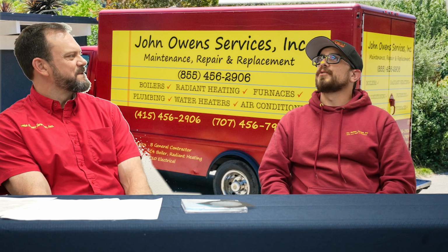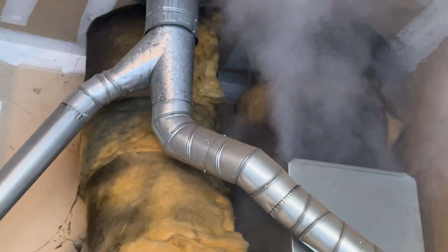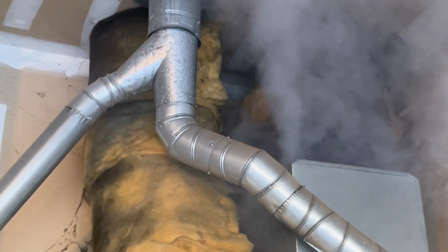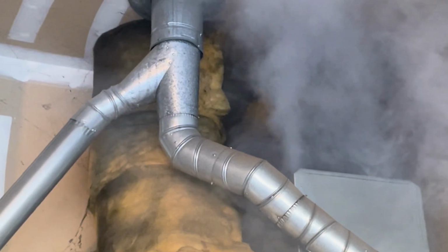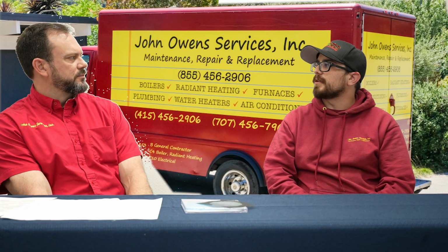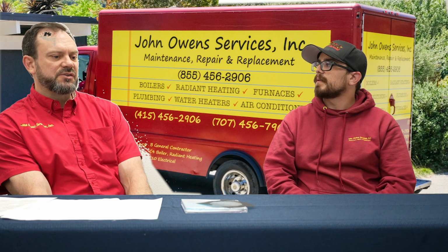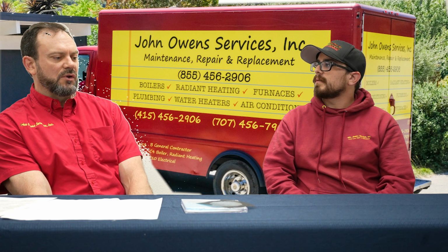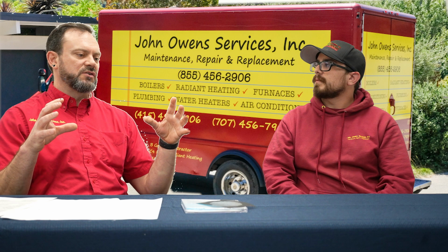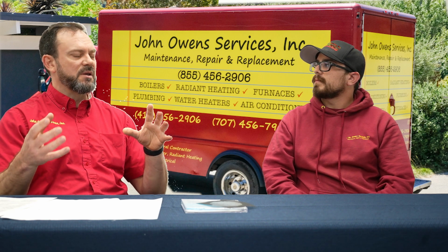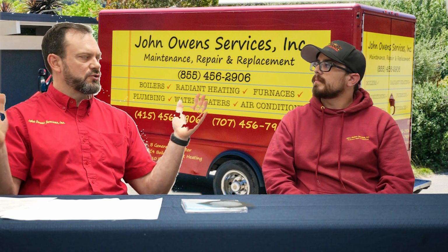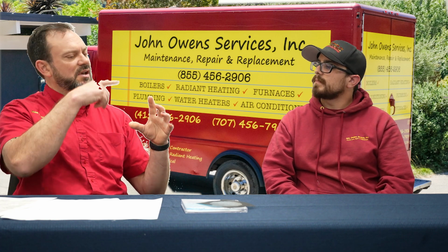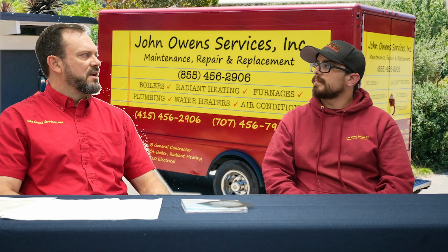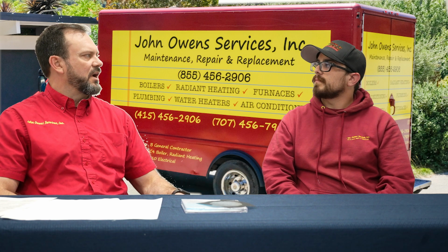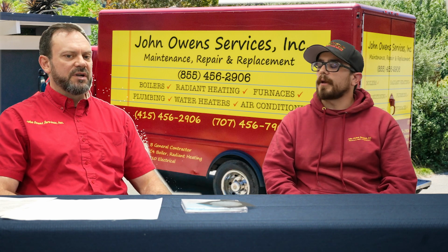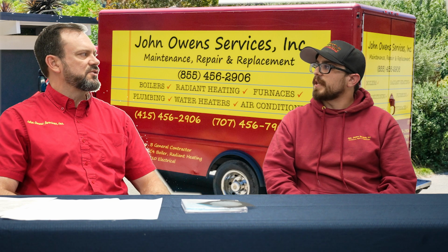I think I was told that if you see your yellow insulation has black markings in it, that's a sign that air is being pulled in, correct? Into your system? Yeah, that's right. You'll see that at every joint where there's connections, maybe a 90 degree turn or just two long pieces tied together. A lot of the time you'll see that black insulation around it. And that could be either from a leak or air blowing out of it. It could be either or. But that's a sure sign that you've got some kind of leak there.